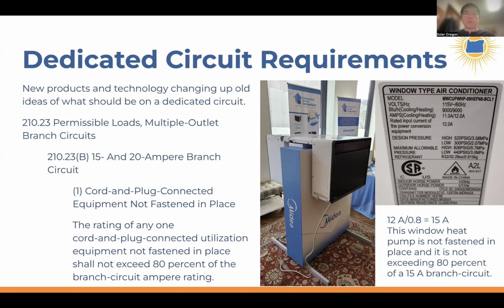The power requirement for these is, on the coldest day when running at 100%, they use 12 amps, and 12 amps is 80% of a 15 amp branch circuit, which is the smallest amp rating in a typical home. The code requirement is that cord-and-plug equipment not fastened in place cannot use more than 80% of the branch circuit. So this one's right at that limit.